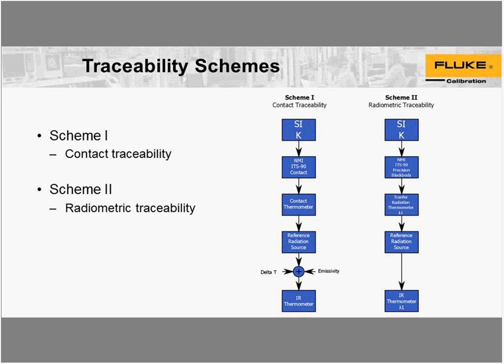If the wavelengths are not similar, we lose traceability. For example, if your transfer standard is a 3.9 micrometer instrument and your IR thermometer is 8 to 14 micrometers, then you should not be doing that calibration — you don't have traceability.